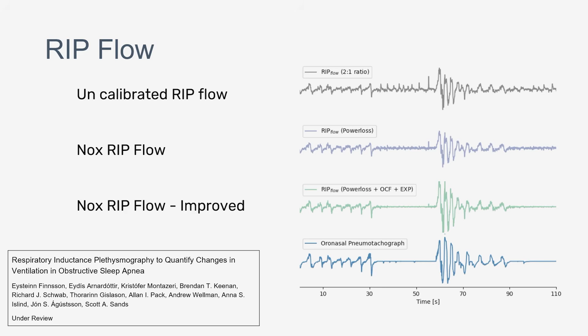So what we're introducing in this paper, and we haven't introduced in our product yet, is an improvement of the RIP calibration. And in this, we can actually get a much clearer picture of the apnea. And what is also important for us is the amplitude of the recovery breath is more closely related to what you see in the oronasal pneumotachograph. So this allows us to get a flow signal from the RIP signals, which tracks much better the oronasal pneumotachograph. So actually, if you can do this, you just have the 2 belts, you can measure breathing like this. Now you have something which is not difficult to wear and can actually give you very good data.